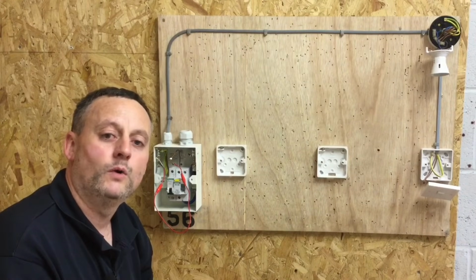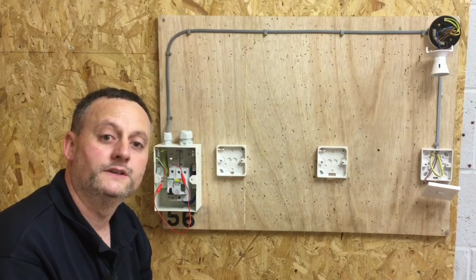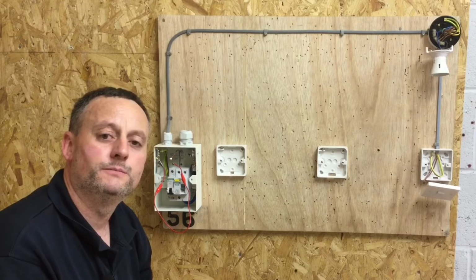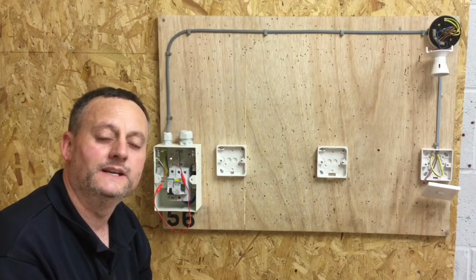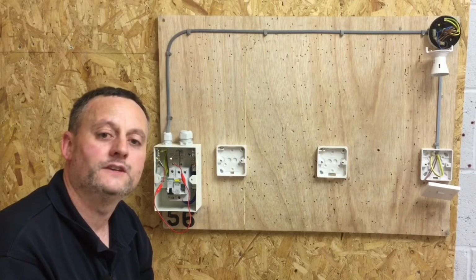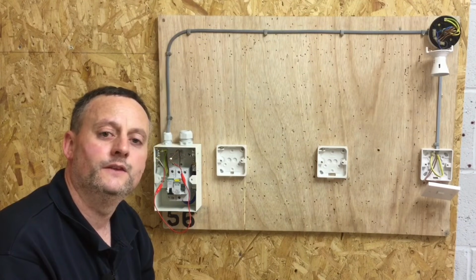Remember, if you have more than one lighting point and more than one lighting switch in a circuit, you must test at every lighting point and every switch on the circuit in order to prove the CPC gets to each point in turn and prove polarity. Recording the highest reading, logically at the end of the circuit on a radial circuit. However, it would be the highest reading wherever you achieved it that you would record.